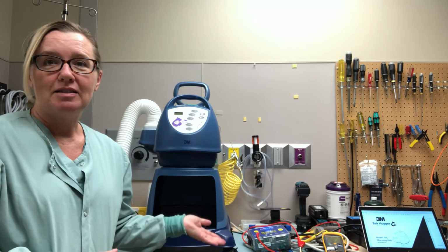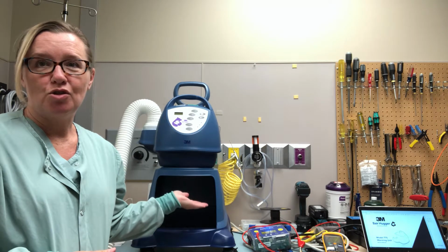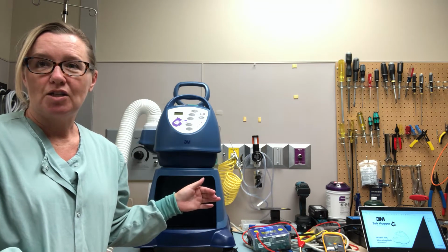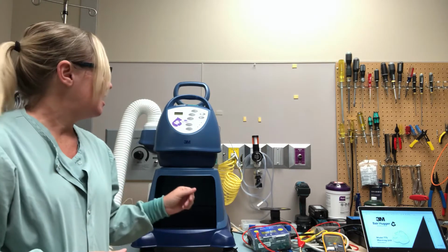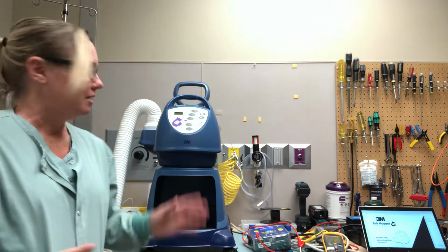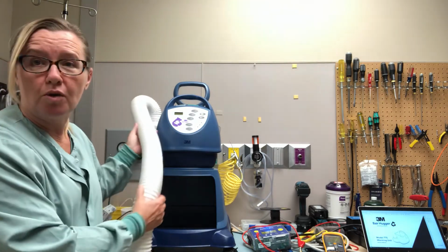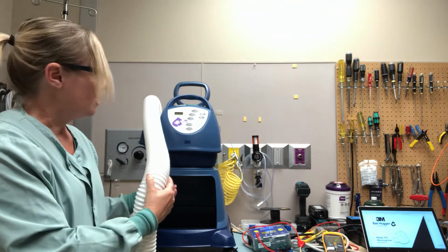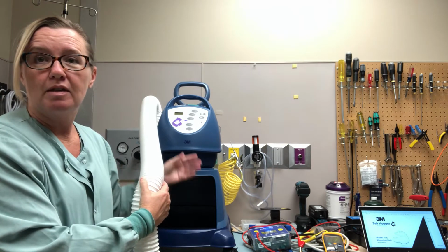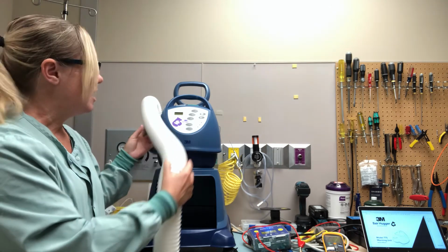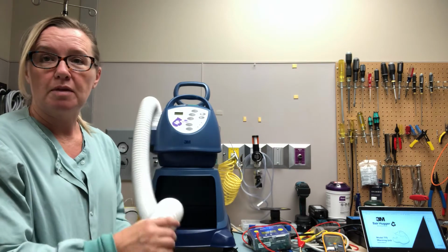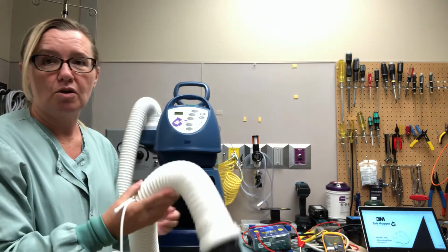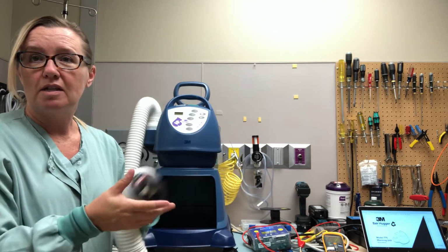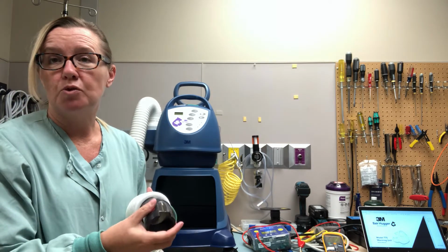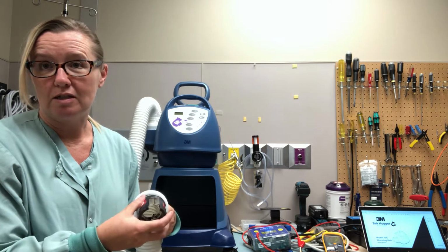So it has some set temperatures that you can choose: 32 degrees Celsius, 38 degrees Celsius, and 43 degrees Celsius. And this operates with a blower, so it's taking room air up through a filter on the bottom into a blower, and it's coming out with the temperature that the user selected through this hose. And this hose connects to, usually, a disposable blanket that's on the patient.